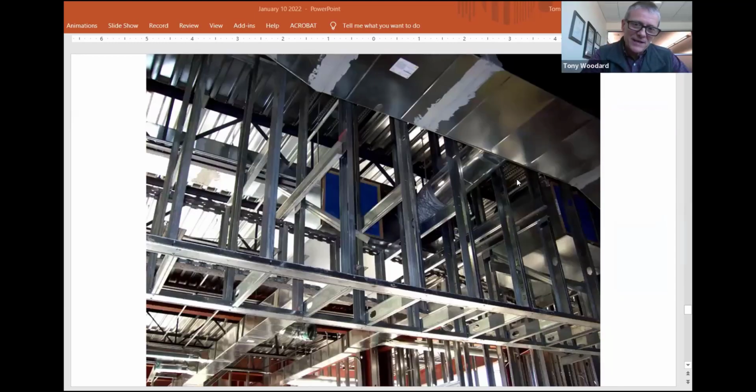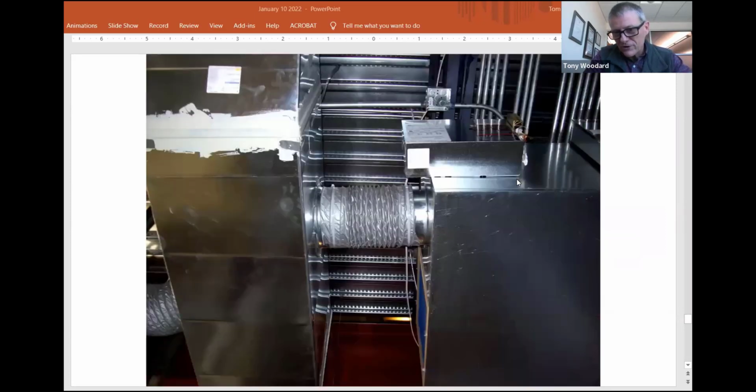Okay, so you're seeing that gray flex connector. You're seeing your main trunk line run through there. How do you get up there and change that air filter once they sheetrock all this in? Because this is not a drop-in ceiling here. This was all going to get rocked in. So it's going to be a little tricky getting up in there to that filter where it needs replaced. They had to come back and build some little access doors to get up through there. But that's showing you it's drawing across that.